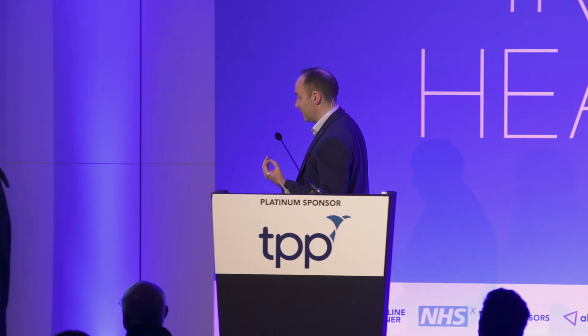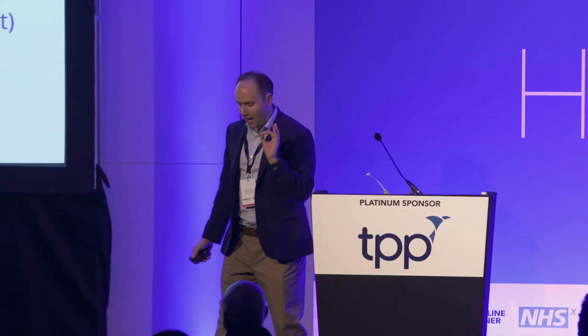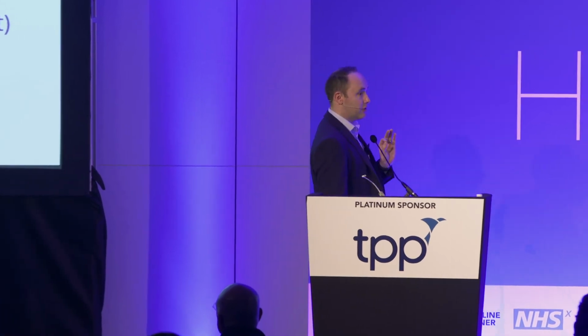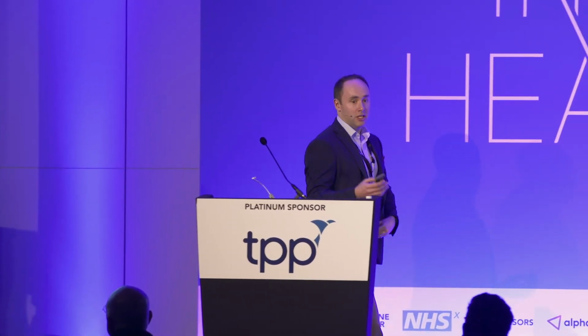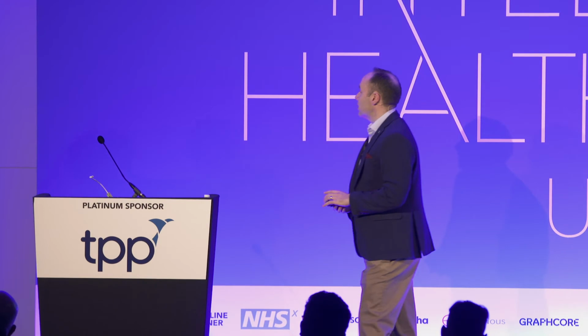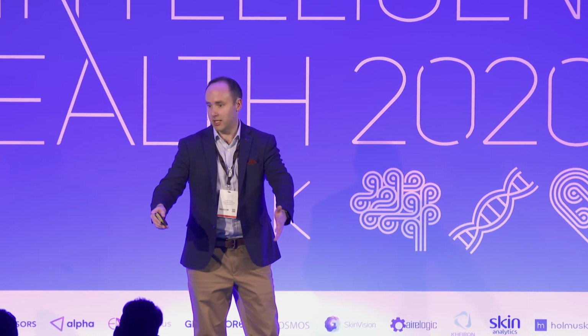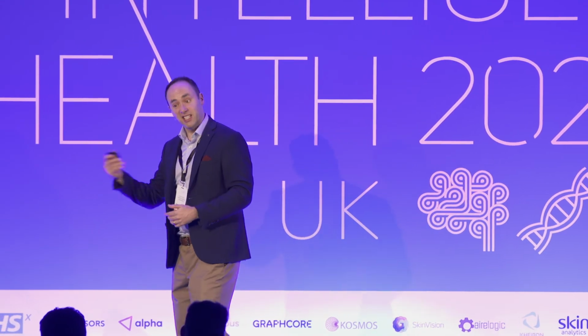Do I need to do a clinical investigation? Not necessarily. You are only absolutely mandated to do a clinical investigation if you are a Class 3 device. Clearly, you don't want to put people inside PET MRI scanners if they've never been tested. And also only if you're a Class 2 device that's based on innovative technologies. Now, AI still counts as new. So every AI device still needs a clinical investigation. And if you have a new intended use that no one has ever before put on the market, then you definitely need a clinical investigation because you won't be able to do a literature review or compare yourself to anybody else. So if you suddenly come up with a new idea that no one's ever thought of, you're not going to get to market that quickly because you still need to do all your studies.